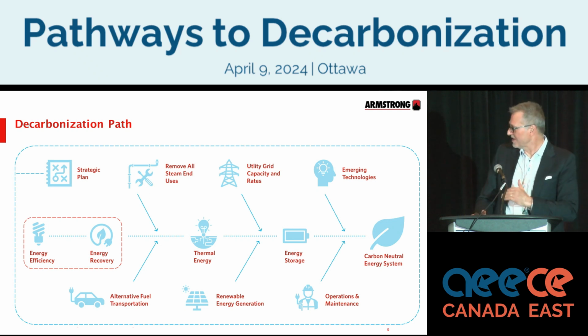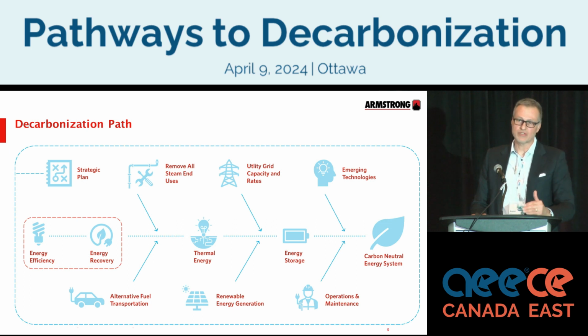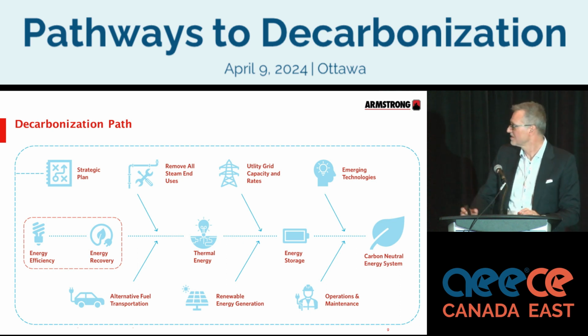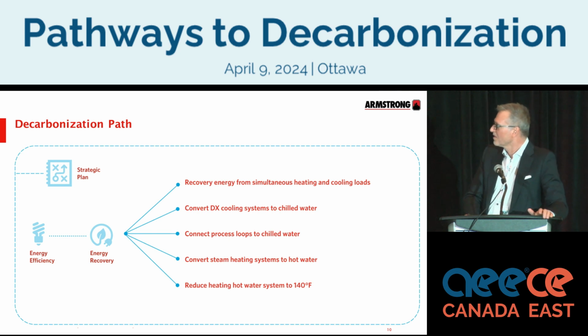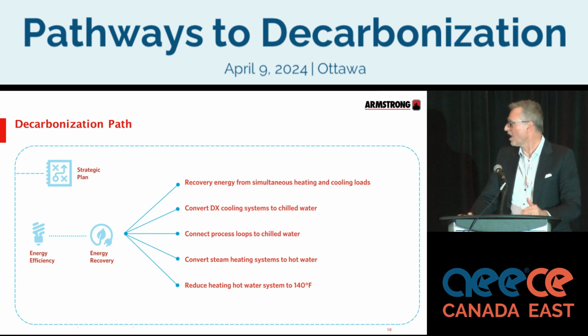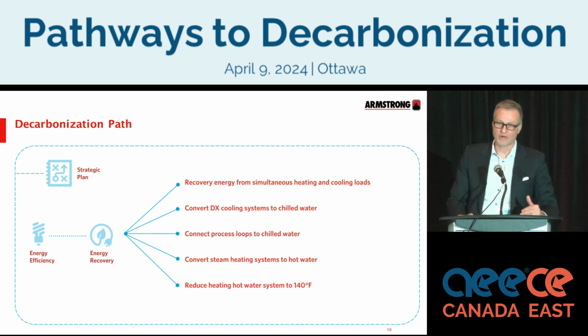But the point being here, then, with operations and maintenance, is how do you capture that knowledge, or how do you improve the performance of your building on a continuous basis? So in that strategic plan, after energy efficiency, when we talk about energy recovery, we're looking at energy recovery from simultaneous heating and cooling systems. Trane has chillers that will do simultaneous heating and cooling applications. We convert the DX systems to cooling systems or chilled water, connect process loops to chilled water, and what that means is now we're capturing more of that thermal energy. Convert steam heating systems to hot water, and reduce hot water systems down to 140 degrees or lower.